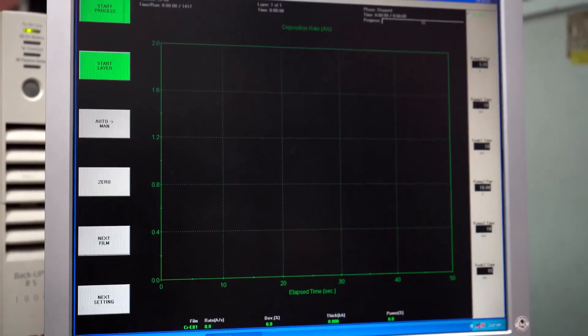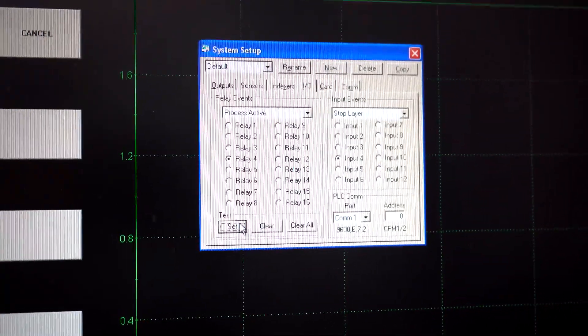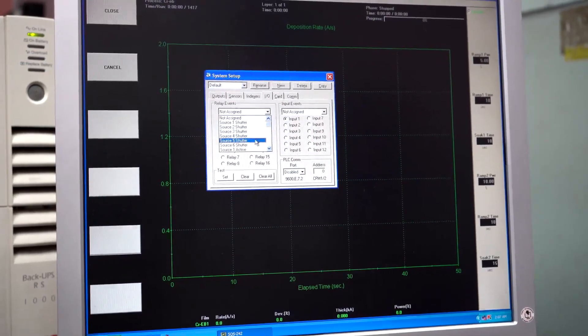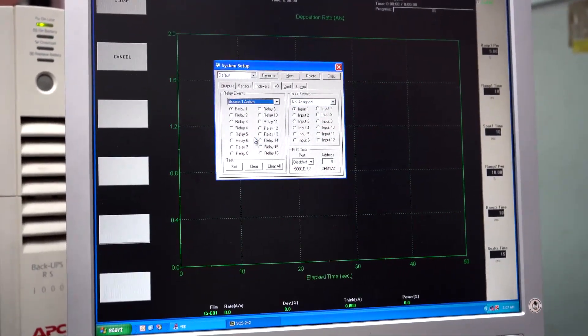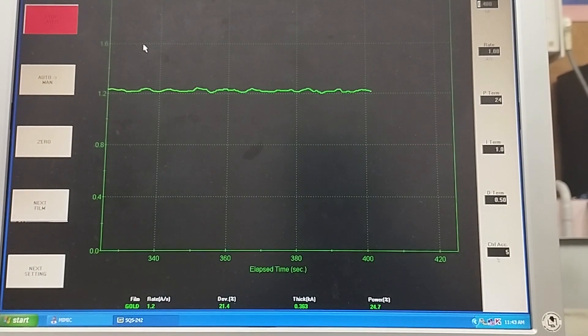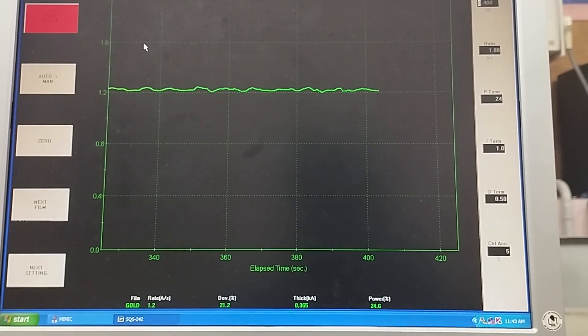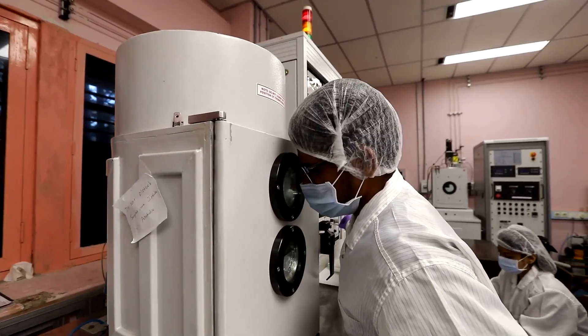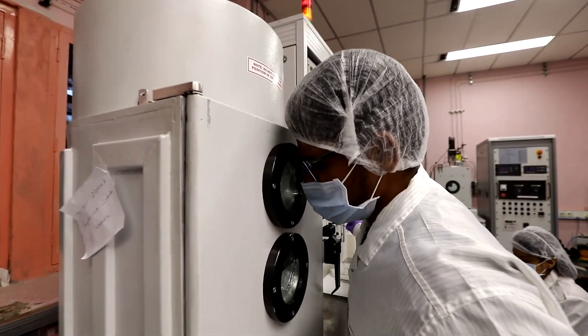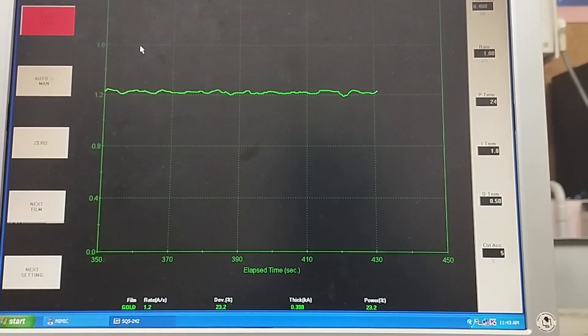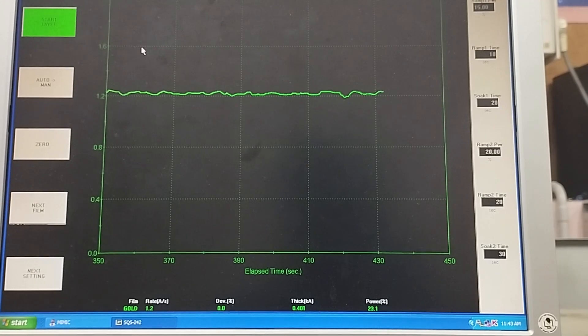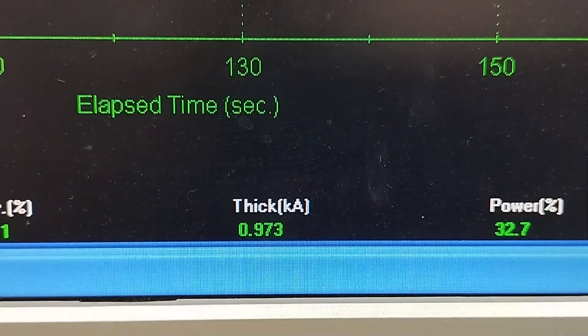Now set the metal and the deposition parameters in the process screen. Then click start process in the software. Deposition will start. From the chamber viewport, we can see the process inside the chamber. When the deposition will be completed, it will automatically stop the deposition.